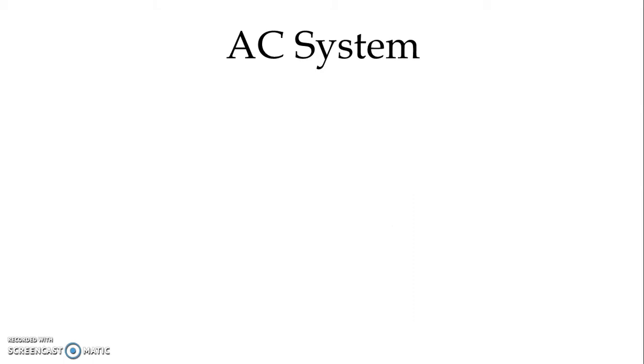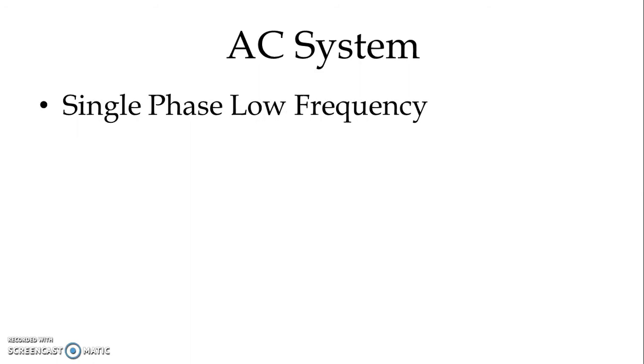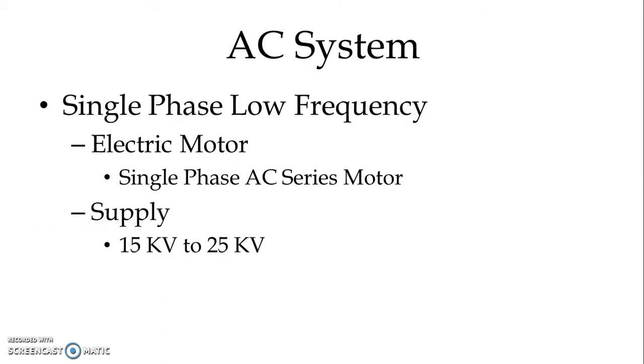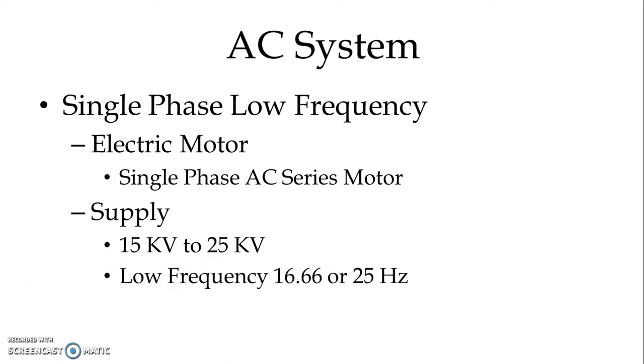We start with the AC system. In the AC system we have three different categories: single phase AC system with low frequency, single phase AC system with high frequency, and three phase with low frequency. Starting with single phase low frequency, the electric motor used for motive power is a single phase AC series motor, and the supply is a single phase high voltage in the range of 15 kV to 25 kV for overhead distribution. A traction substation is used to feed the distribution network.